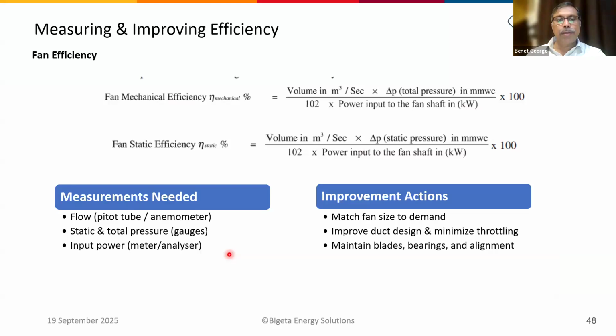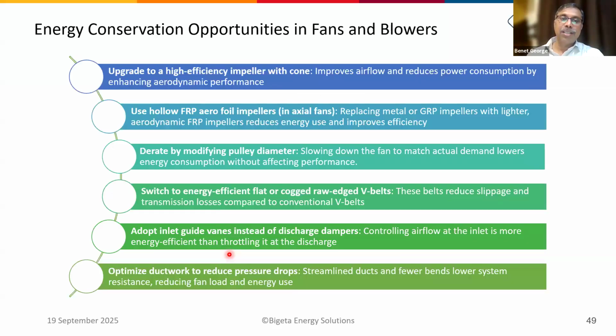So similar to the pump, we can calculate the efficiency of the fans based on volume and delta P. Here, in a similar way, suction and discharge pressure in mm of water column, divided by 102, into power input to the fan shaft. So we can compare the actual efficiency with the design efficiency. And also we can see whether high efficiency fans are available for that particular application. For measurement of parameters, we can use a pitot tube or anemometer or a manometer for pressure and a power meter for input power. So these are some of the opportunities in fans and blowers.